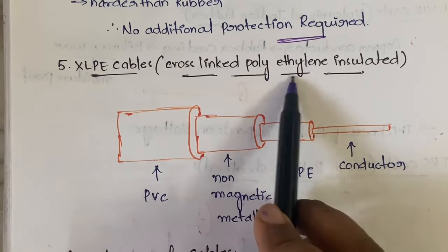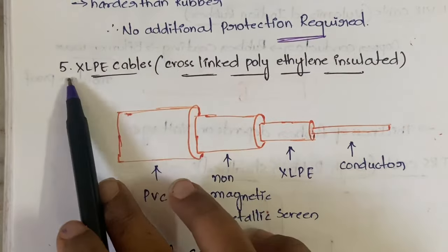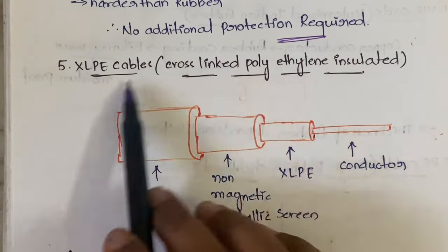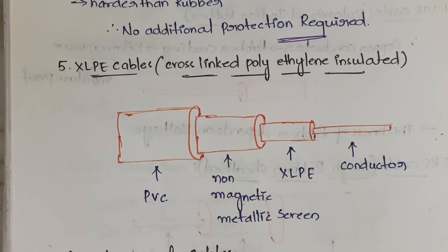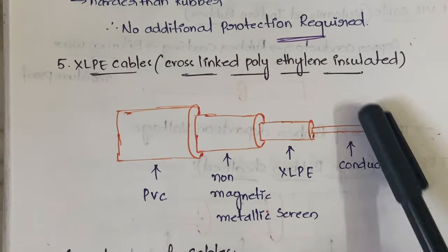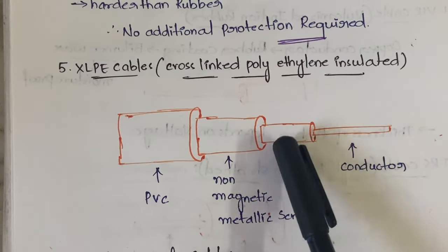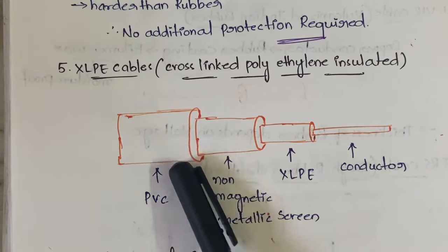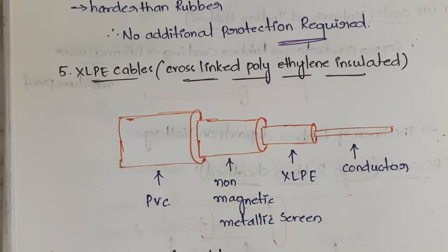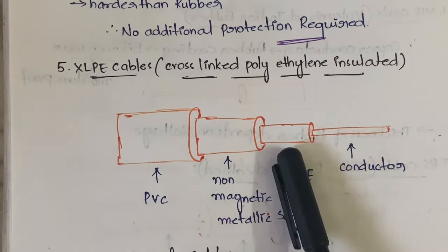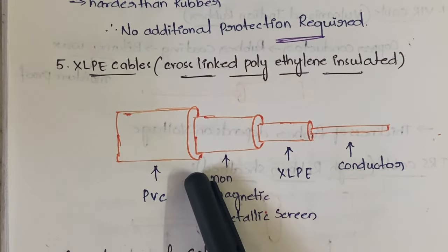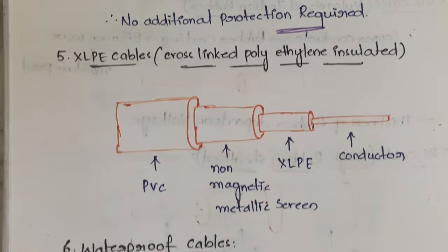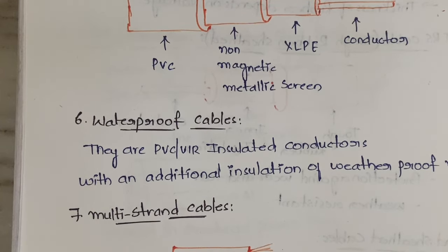The fifth type is XLPE cable — Cross Linked Polyethylene insulated cable. Here the conductor is coated with XLPE, around the XLPE there is a non-magnetic metallic screen, and around that is a PVC coating. XLPE cables are very strong because of these multiple layers: conductor, XLPE, non-magnetic metallic screen, and PVC.